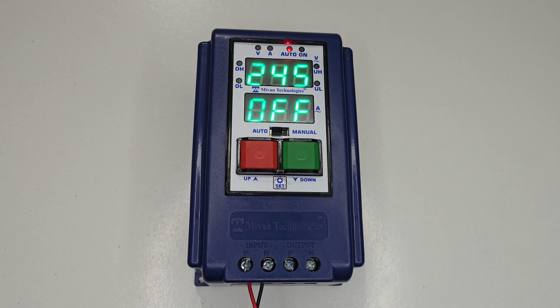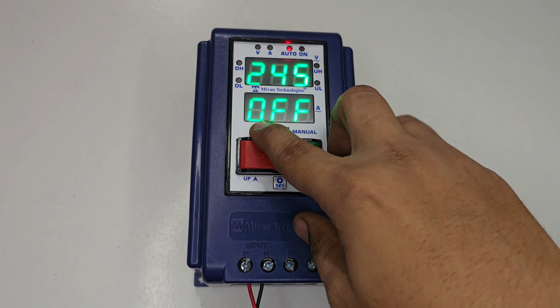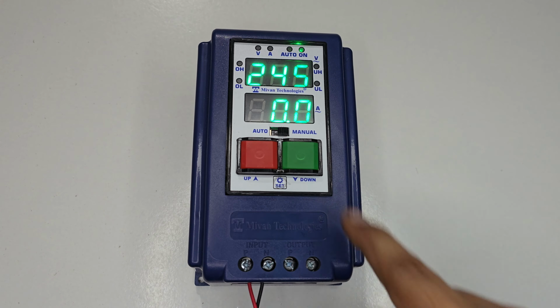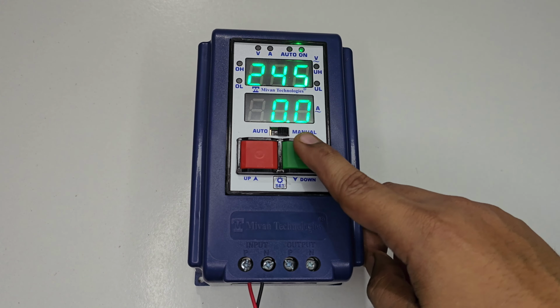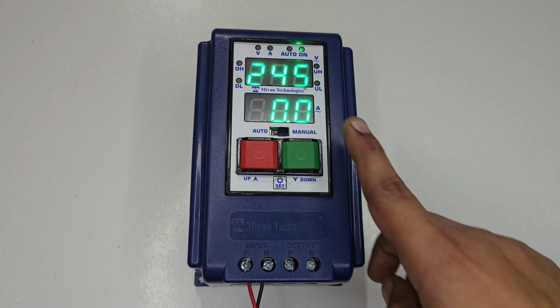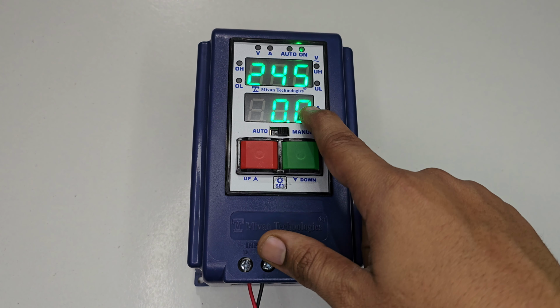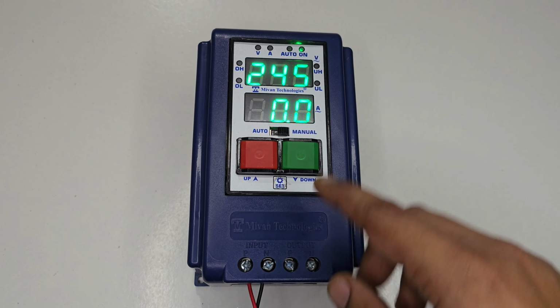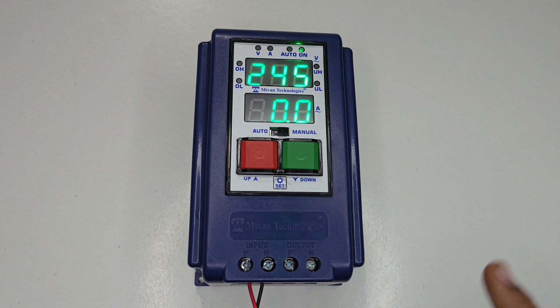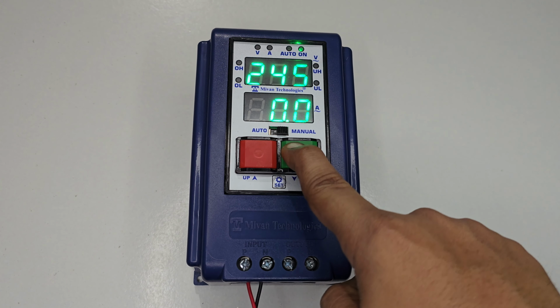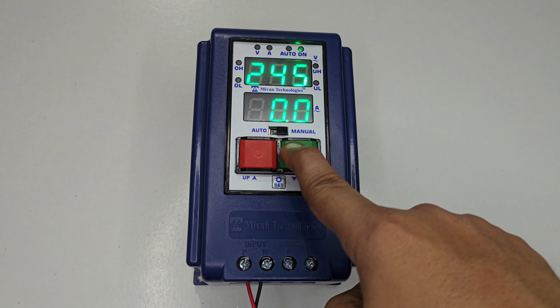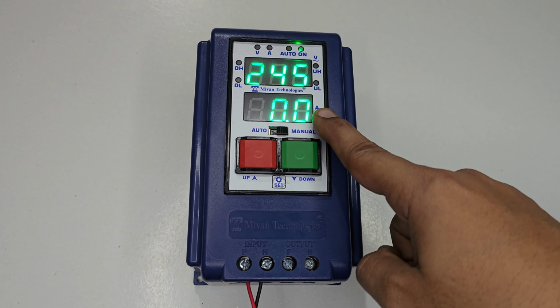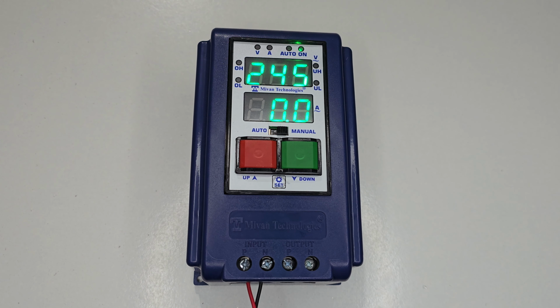Now I'll show you how you can set the overload and dry current automatically. To set the overload and dry current automatically, first put the device in manual mode. Press the start button. The on indication comes and here you can see the load in ampere. I have not connected anything, so it is showing 00. If you connect a motor, it shows some ampere here. Once that ampere gets steady, press the green button for 5 seconds. You can see the OL set message. Once you can see the OL set message, your overload and dry current are adjusted automatically.